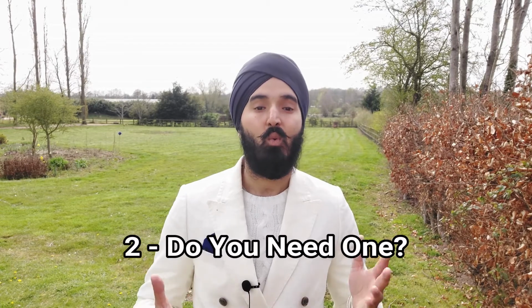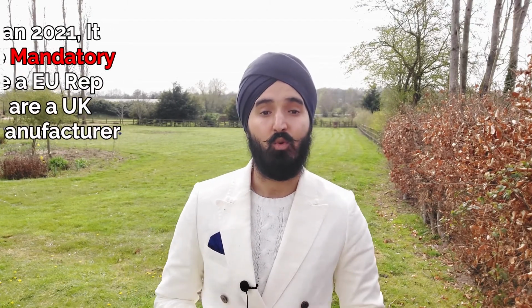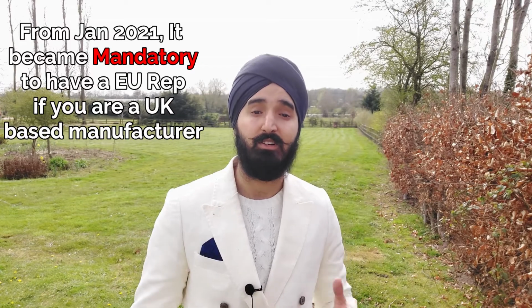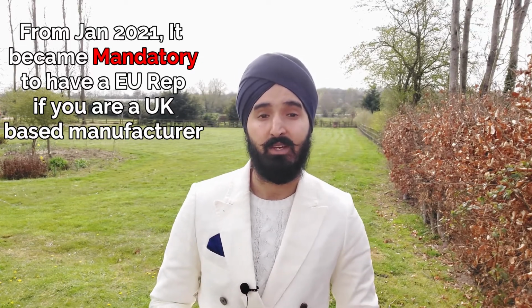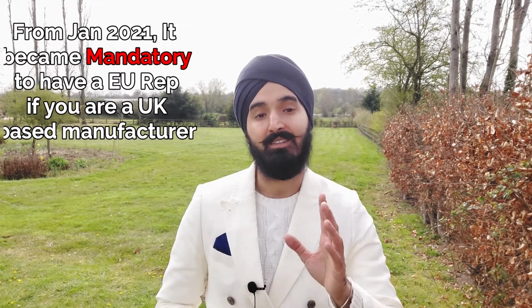Number 2. Why do you need an EU Authorized Representative? For non-European Union-based manufacturers, it is a legal requirement to appoint a suitable EU Authorized Representative prior to placing their products onto the market within the European Union. If you are a manufacturer based in the Union or have no intention of selling there, then you are exempt from this requirement.